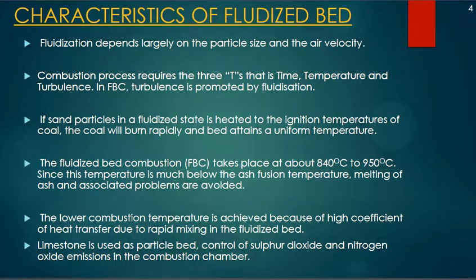This lower combustion temperature is achieved because of the high coefficient of heat transfer due to the rapid mixing that is happening in the fluidized bed. Limestone is one of the important constituents used as a particulate bed, and this controls the emission of sulfur dioxide and nitrogen dioxide in the combustion chamber.